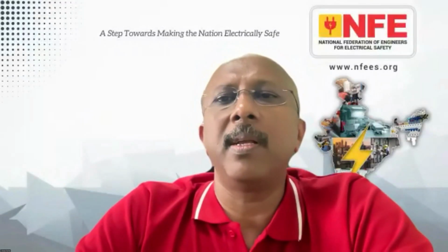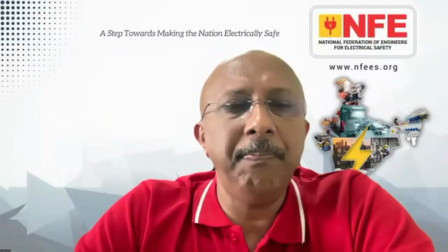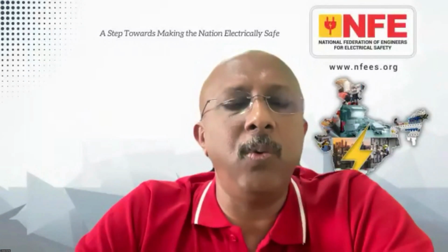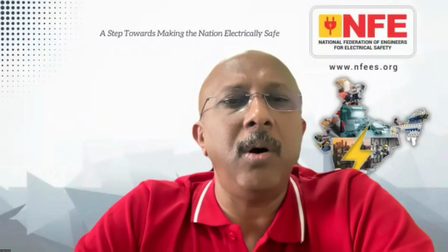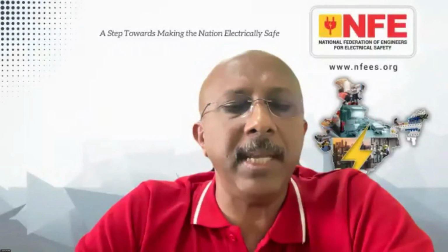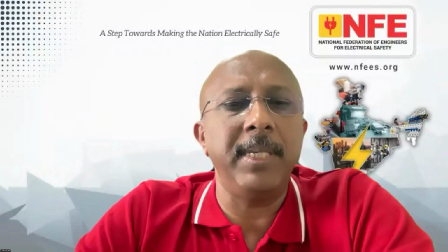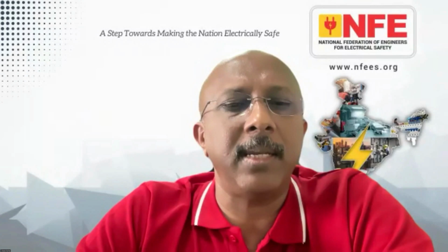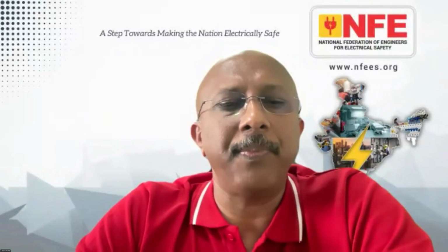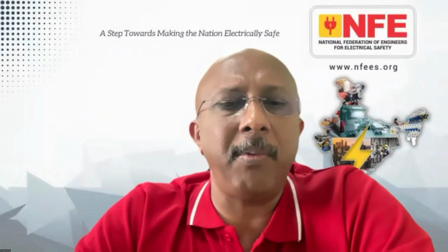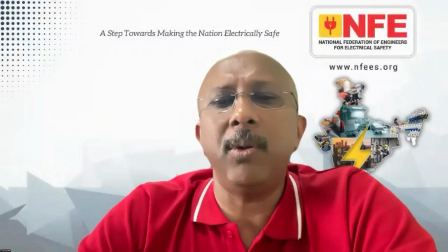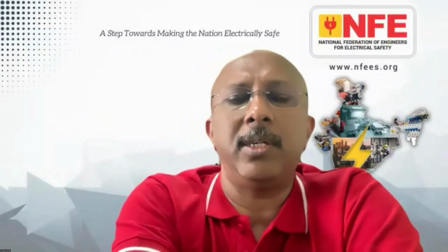Abhijit Lime is saying, can you, in short, explain the difference between arc fault and arc flash? There is a lot of ambiguity in the terminology. Yeah, arc fault is a simple fault created in low voltage wiring due to a loose contact or some simple reasons. Basically, it can be series or parallel. Series means there is a loose contact, and as a result current is jumping through the loose wire. It's limited, in a very small area. Probably you may not be able to even identify it. But over a period of time, this may create a fire situation.